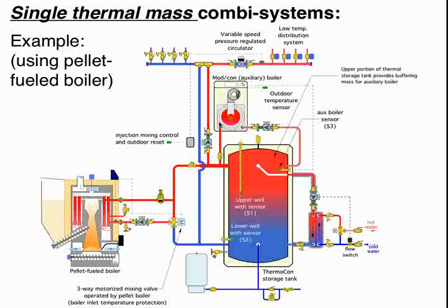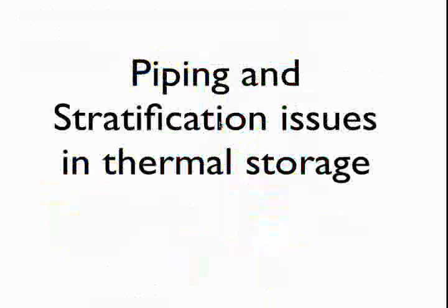And the heat sources, basically this would be the priority heat source. The auxiliary heat source, the ModCon boiler, would just come on if and when the pellet boiler cannot keep up with the load, or perhaps in the summer you choose not to fire the pellet fired boiler, in which case the ModCon boiler could take over. So it's a nice concept. It's relatively simple piping there.